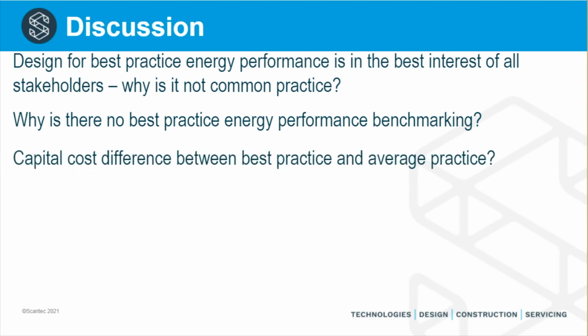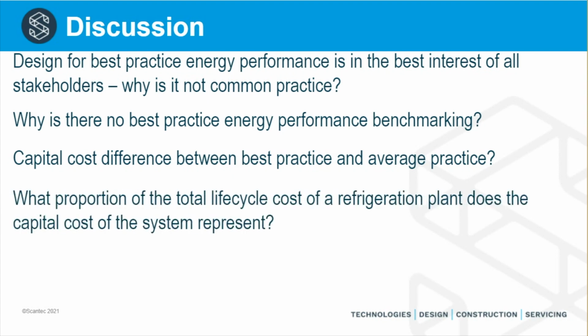What is the capital cost difference between best practice and average practice? No more than 15% in my experience between a liquid overfeed system and a centralized low charge ammonia system. So that 15% has a very quick return on investment. And what proportion of the total life cycle cost of a refrigeration plant does the capital cost of the system represent? If you don't know the answer to that question, I'll volunteer the answer here. It is approximately 10%. In other words, the cumulative operating cost of a refrigeration plant is 10 times higher than the initial capital cost. Yet in the vast majority of cases, the buying decision is based on the capital cost of the system and not the cumulative operating cost or life cycle cost.